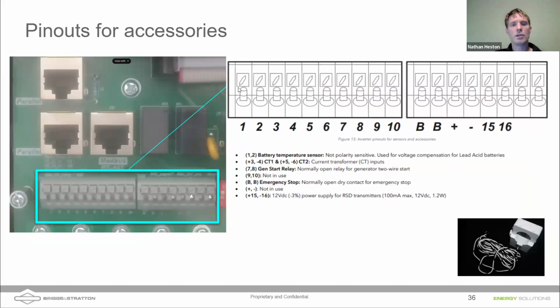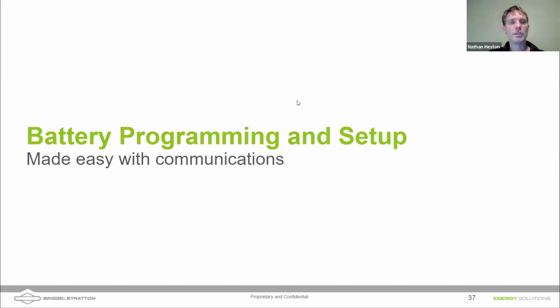The pinout for accessories here, some things to note. The emergency stop is the 2 terminals, 11B, 12B, that are here. And you would wire your 2-wire stop button to that. I believe you only need 1 button, even if you have paralleled inverters. Otherwise, you could wire it in parallel, what you need to do if you're doing one of our Briggs inverters. Also note that the 3, 4, 5, and 6, these are your CT sensors, so you can monitor the amount of current you are pulling from the grid and export that same amount from the inverter to prevent pulling from the grid. So this way you can keep that grid import down to 0 and essentially off-grid yourself even when using a grid-tied inverter. So the pinouts are here just so that you have them for reference.